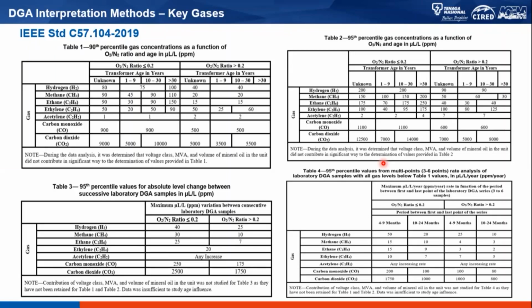Also with this ratio, we know that oxygen and nitrogen are part of the composition of air, and in normal condition, the ratio between nitrogen and oxygen is fixed. But whenever oxygen is consumed within a transformer, this ratio will be different or reduced, and because of that, it will also be very useful in terms of finding out what is happening inside the transformer.